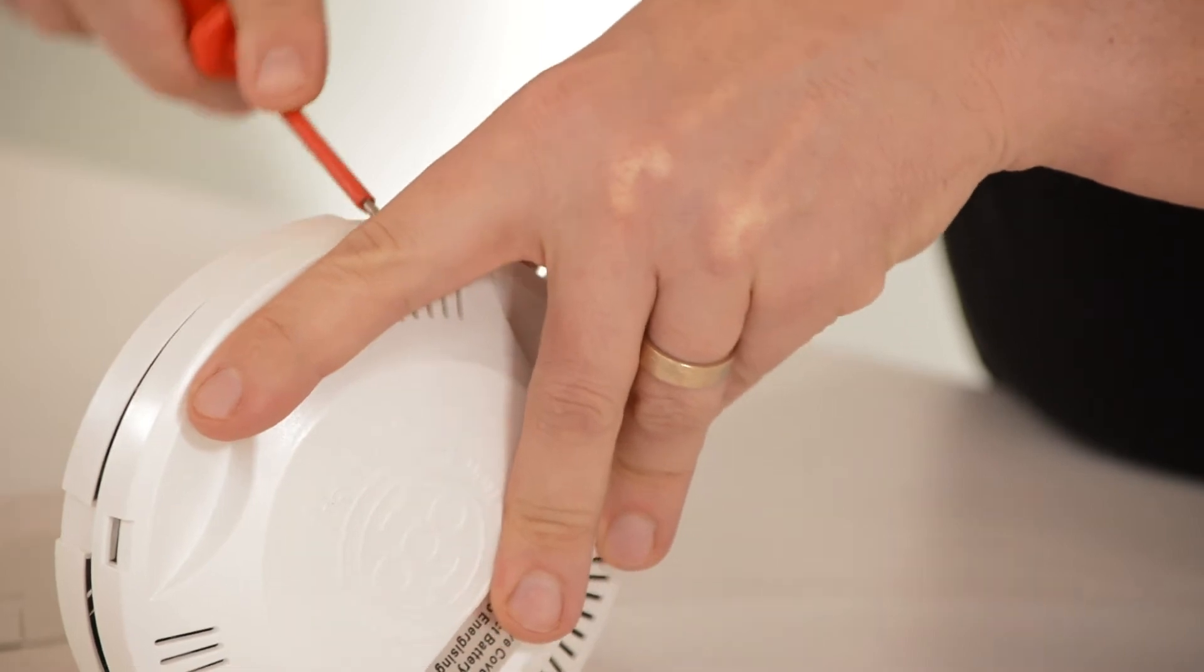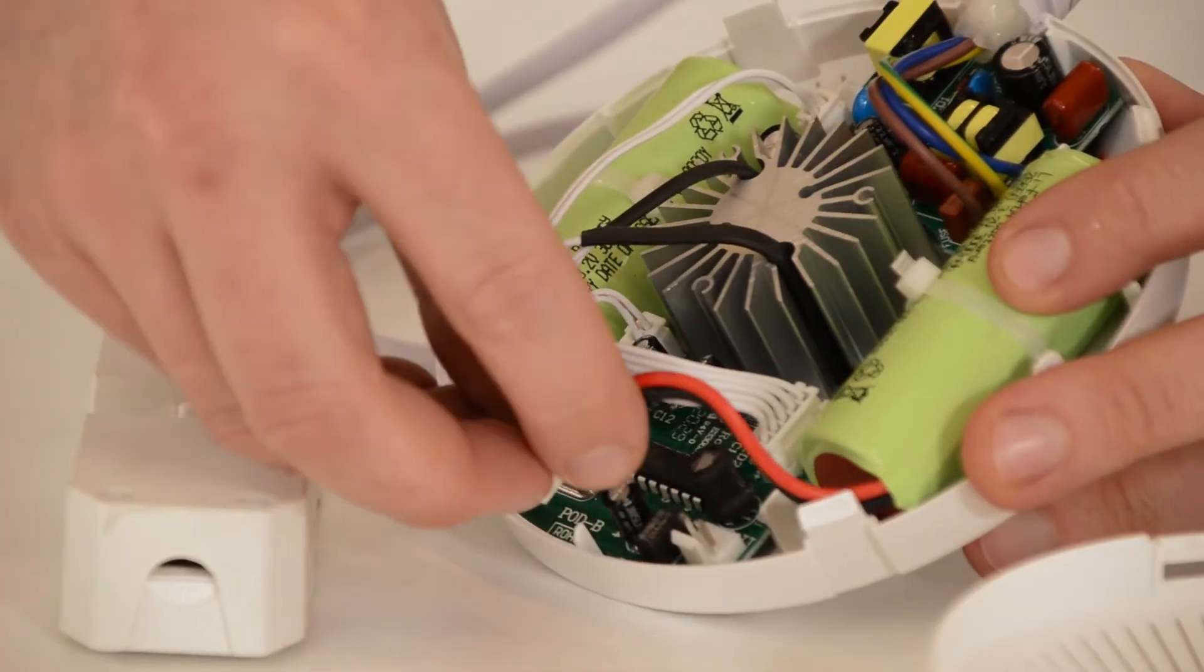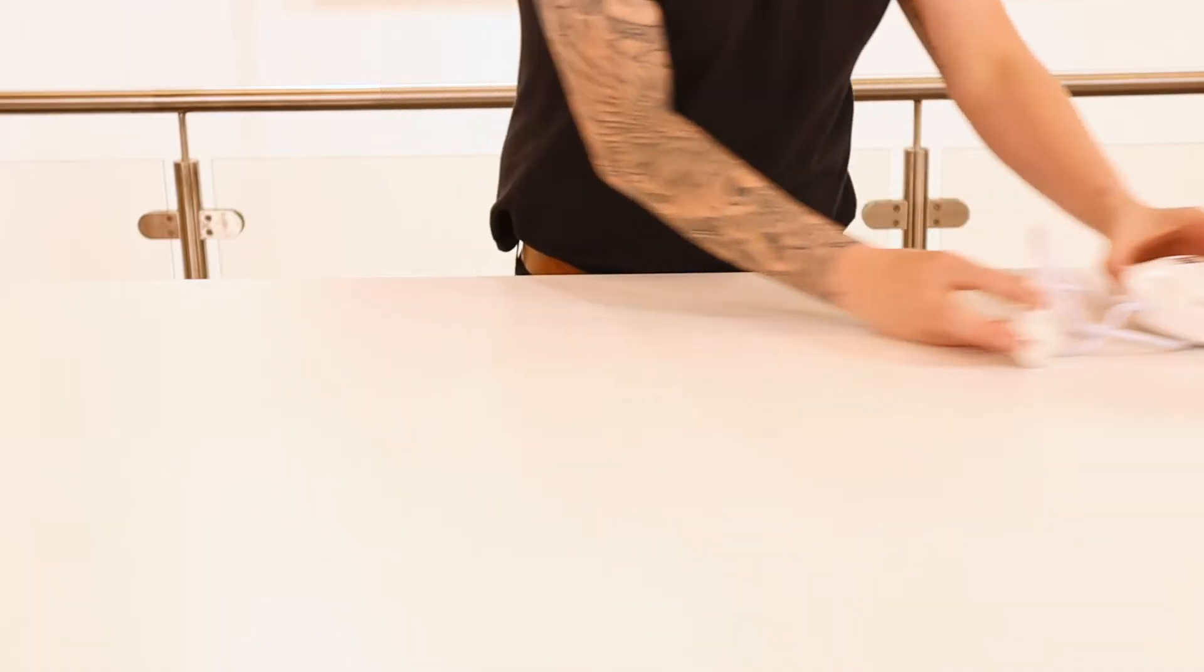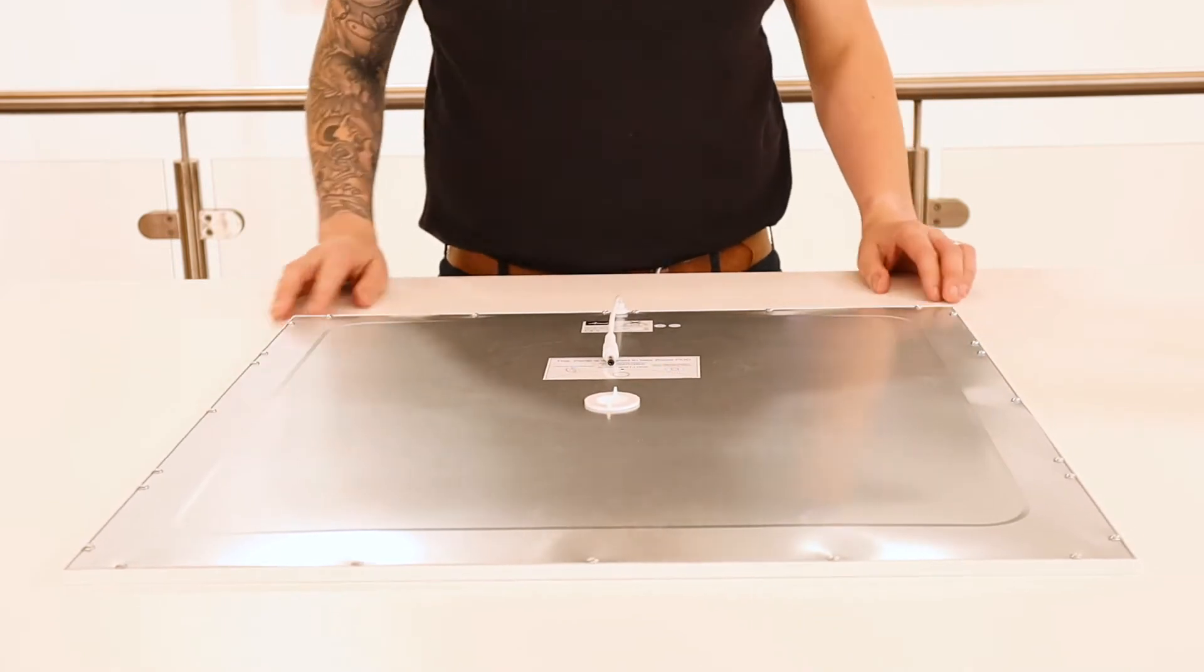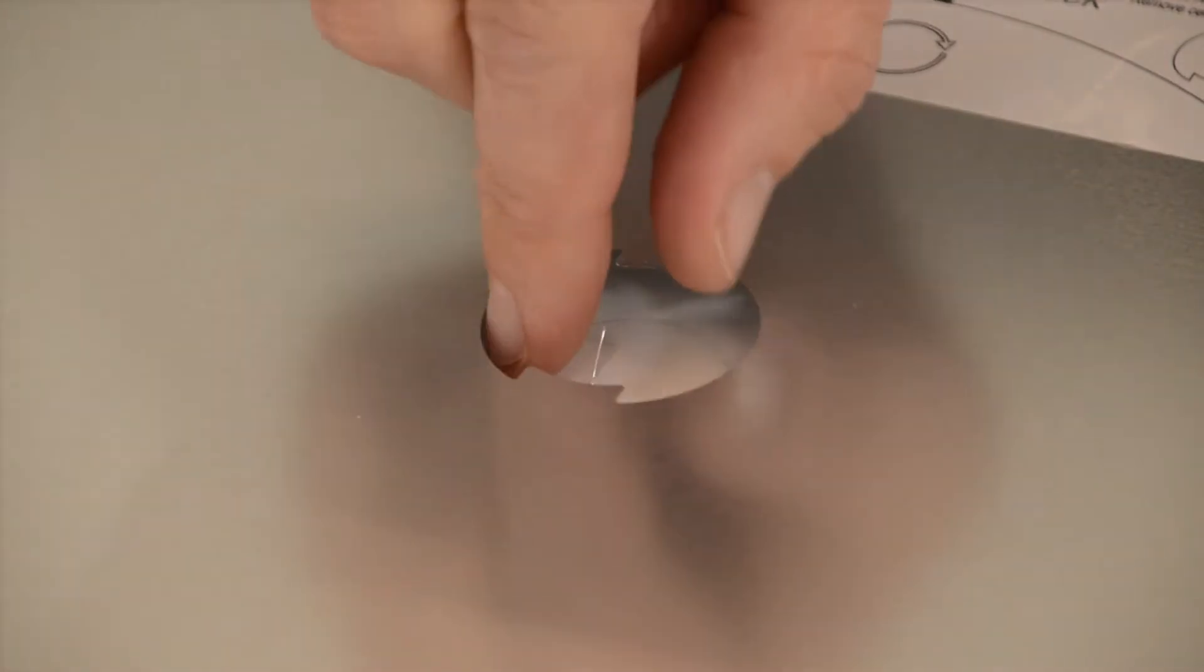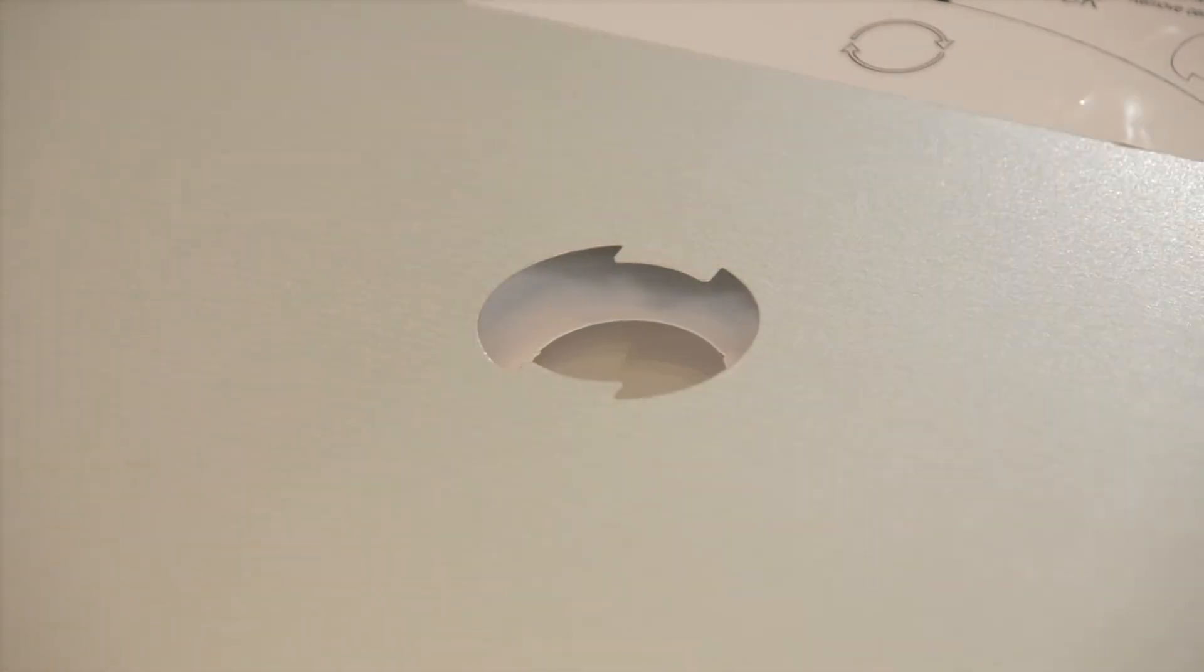To install the PanelPod emergency, first open the PanelPod housing and connect the battery which is supplied disconnected. Locate the installation hole on the back of your designated Ansel panel and remove the blanking coin plug. Then you also need to remove the pre-punched reflector sheet cutout.